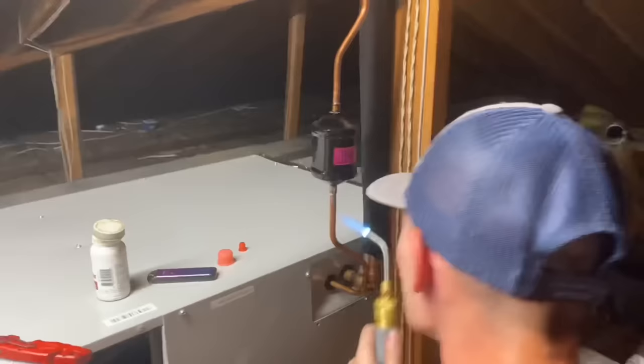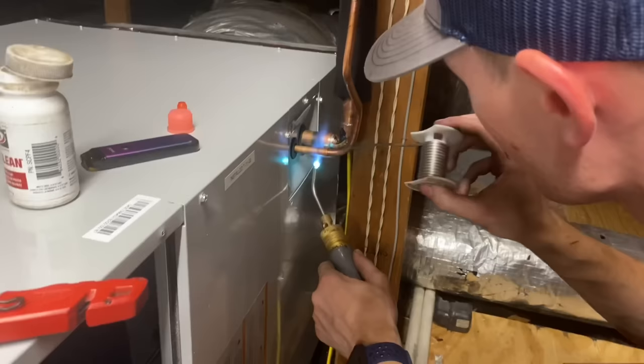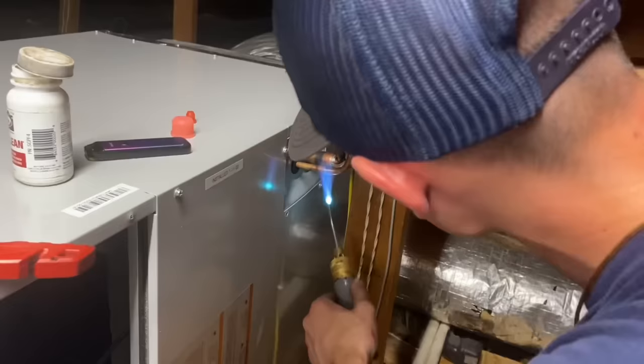You'll see right now, Daniel's using the Harris Corporation, the Stay-Brite 8. You don't have to braze, which means you don't have to flow nitrogen through the system. We're using a standard D tank, but we're not using our typical solder. We're using Stay-Brite 8, special safety flux. And it really, really does a nice job. All right, one less contaminant to worry about.